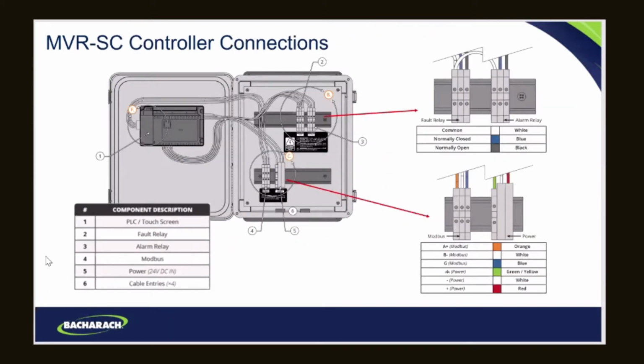This is an open network. Modbus RS-485 has been used for years and years and years in building automation. You know, the newer networks are things like BACnet and some of the proprietary stuff that you get from the Emersons or the Johnson Controls or people like that. But no, Modbus is completely open. Tools are free to use. There's all kinds of libraries and user groups and stuff online, and you can get all the information you want.